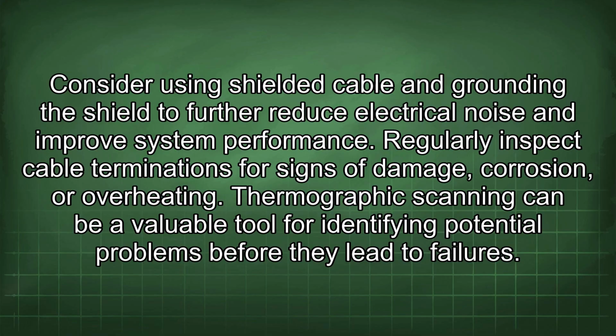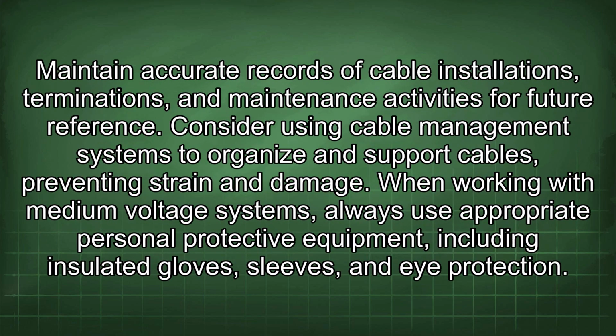Regularly inspect cable terminations for signs of damage, corrosion, or overheating. Thermographic scanning can be a valuable tool for identifying potential problems before they lead to failures. Maintain accurate records of cable installations, terminations, and maintenance activities for future reference. Consider using cable management systems to organize and support cables, preventing strain and damage.